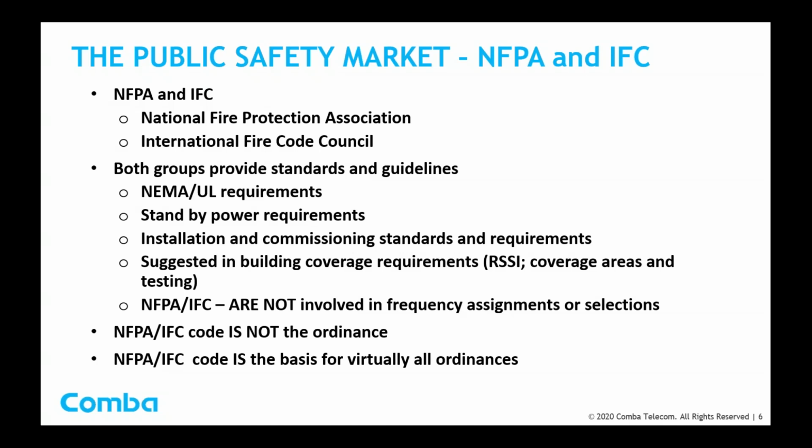They provide standards and guidelines on what area of the building should be covered, what the signal strength should be. NFPA, IFC are not involved in frequency assignments or selections. Understand that NFPA and IFC code is not the ordinance, but their standards generally, as we mentioned, are the basis for virtually all ordinances that are in use today.